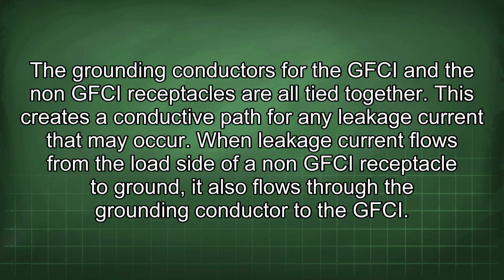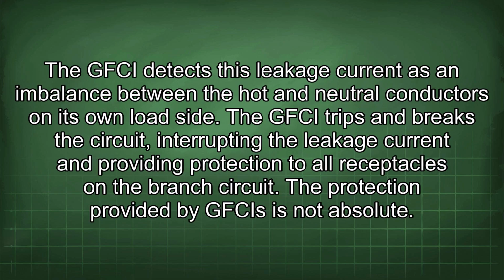This creates a conductive path for any leakage current that may occur. When leakage current flows from the load side of a non-GFCI receptacle to ground, it also flows through the grounding conductor to the GFCI. The GFCI detects this leakage current as an imbalance between the hot and neutral conductors on its own load side. The GFCI trips and breaks the circuit, interrupting the leakage current and providing protection to all receptacles on the branch circuit.